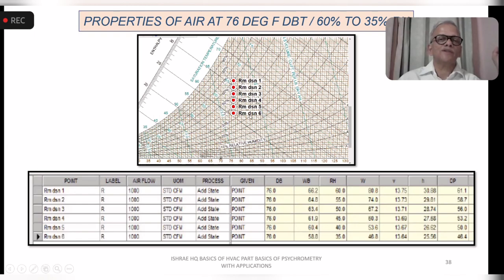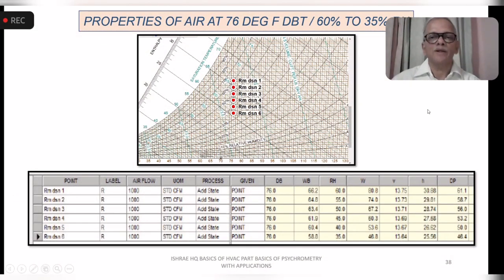So for room design condition 6, the dew point of the air is 46.4. That will be the line which will be meeting here at 46.4, which means if you want to achieve this room design condition, the air being supplied to the space has to be at a dew point temperature or moisture content corresponding to these values, which means you will have to remove a lot of moisture to make sure that you have the correct supply air condition to the space. As you go to higher humidity, you are allowed to operate at a slightly higher dew point temperature. So a higher dew point temperature will give you a benefit in the refrigeration system, but will give you a disadvantage in the airflow rate of the air handling unit.